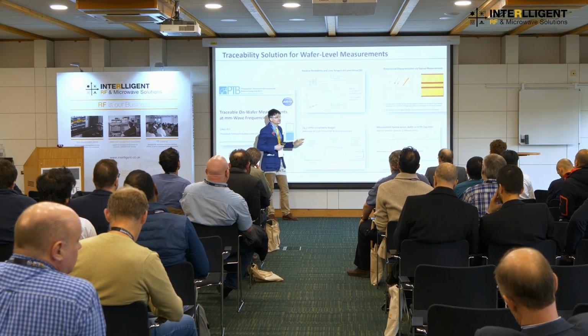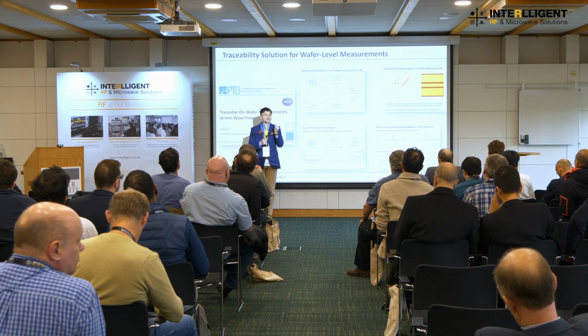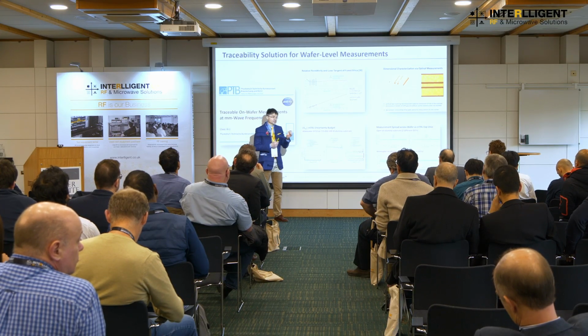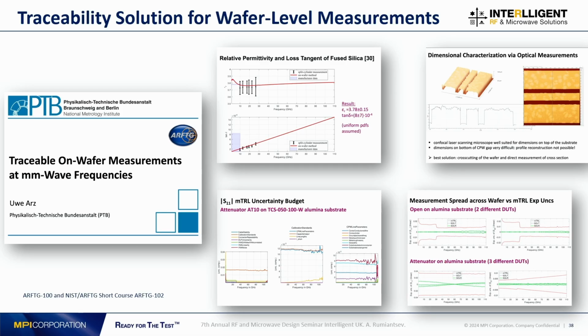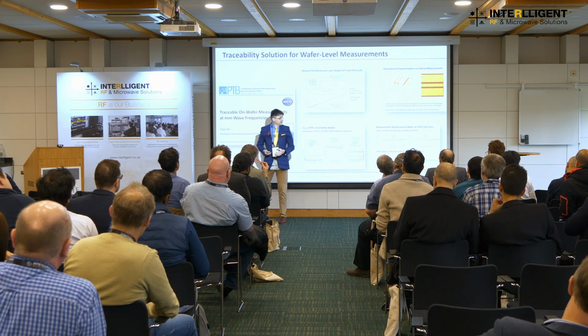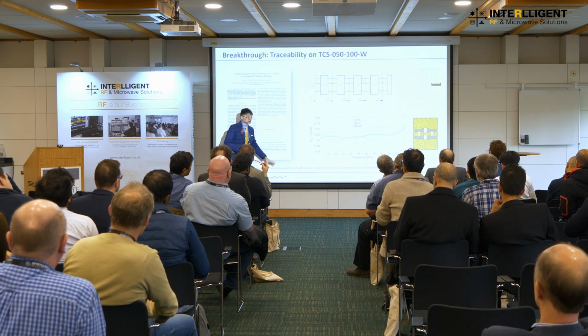And last but not least is an analytical calibration solution, which is implemented in the software from METAS VNA Tools, which helps you to collect all this data and propagate it through the measurement experiment down to your device under test S-parameter correction.